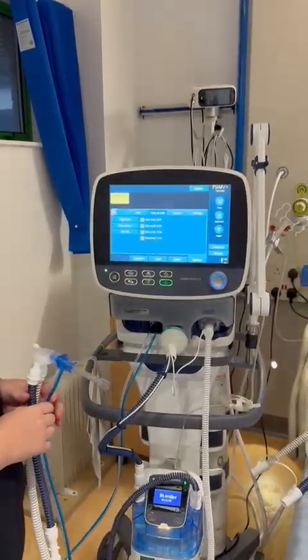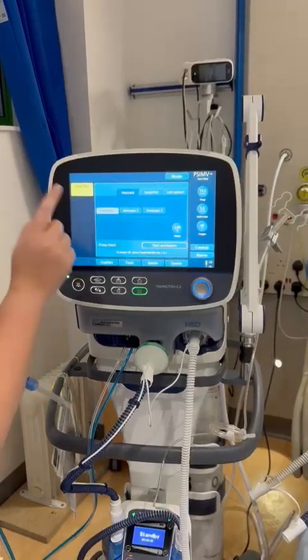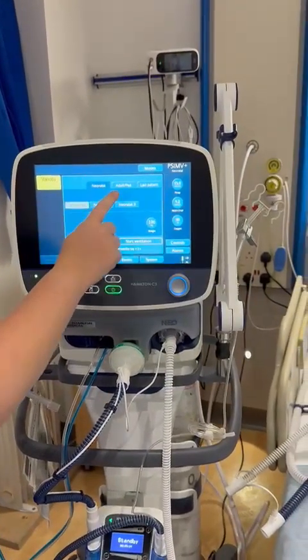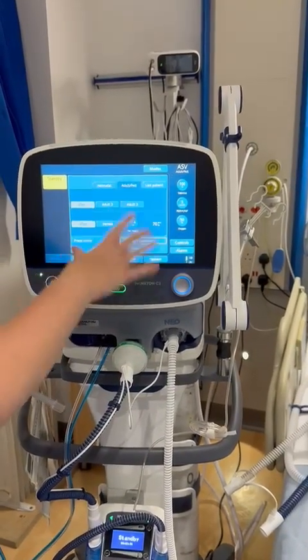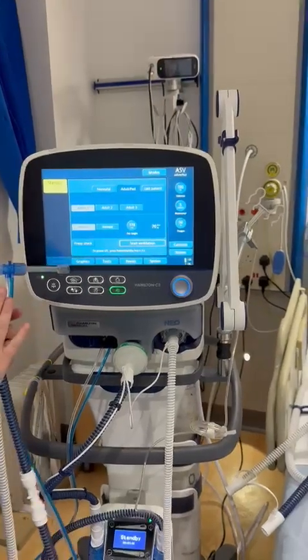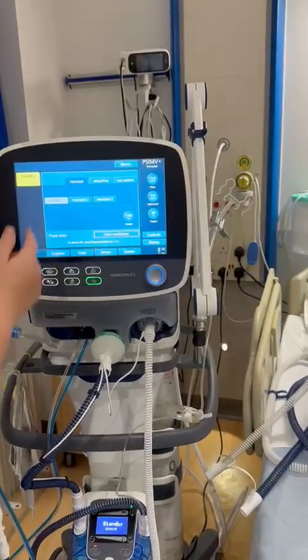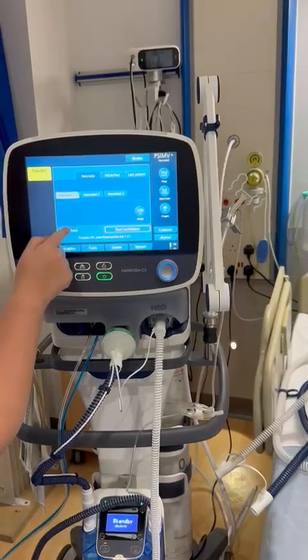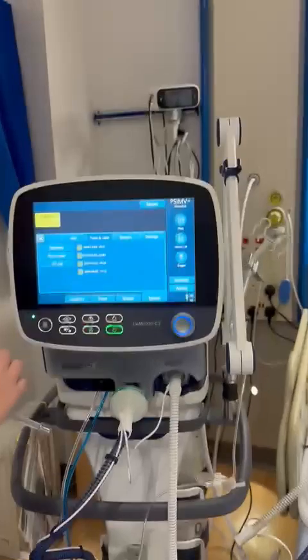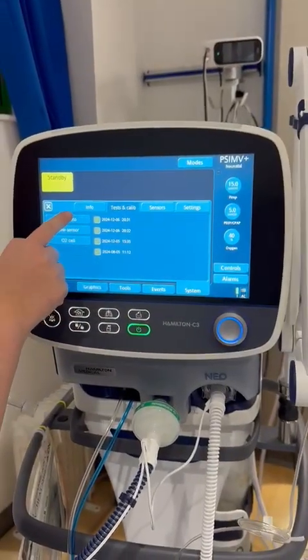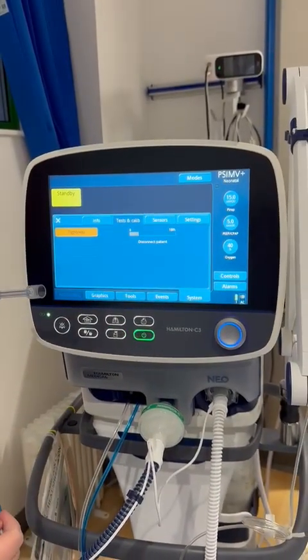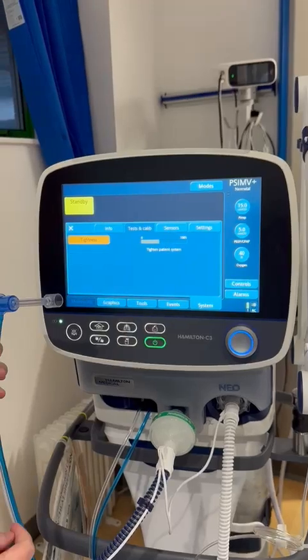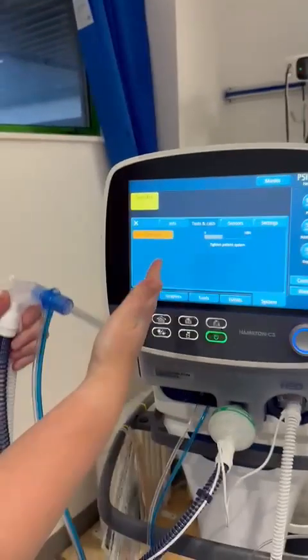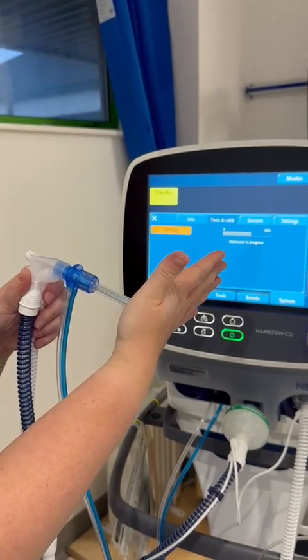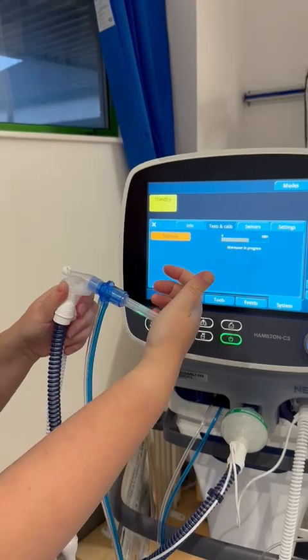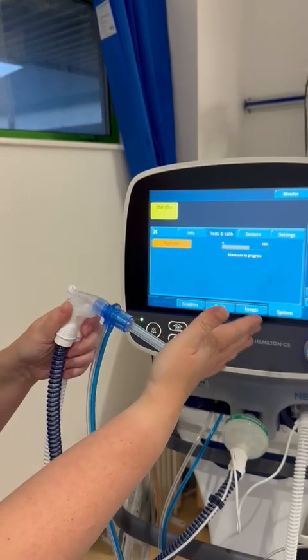So clip pre-op check. Make sure you're on the right circuit at the top. Sometimes it will already be on adult circuit. So if you are using neonatal, you need to just make sure you are definitely on neonatal circuit. Otherwise it won't let you do your checks. So for tightness, press tightness. And then just put your hand over so you occlude it. And wait until it tells you to connect patient, and then you can let go.